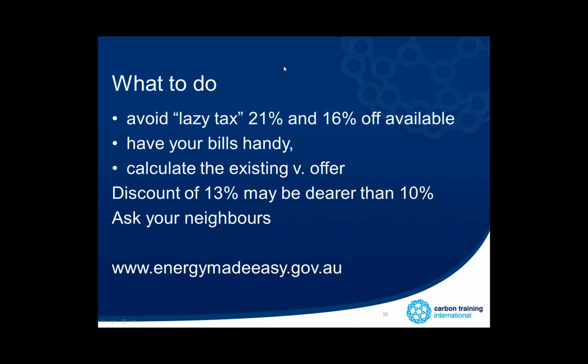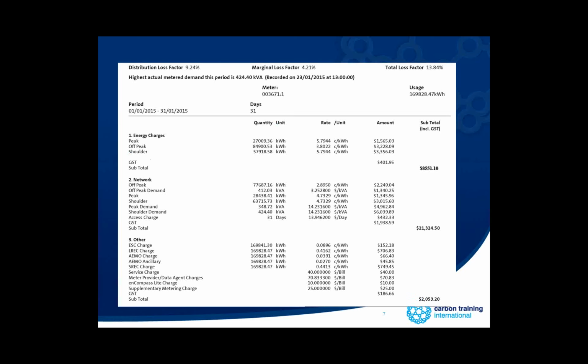Yeah, so I'll just flick back to that relevant slide with the time of use. So the demand charge refers to this kVA, and the kVA is a different way of putting kilowatts. So if I've got a 100 kilowatt electric motor, then the kilowatt reading, if I run that for 1 hour, that 100 kilowatt motor will use 100 kilowatt hours. Now, because electric motors use magnetic fields and induction to basically cause that electromotive force, some of the energy that's supplied to that motor is lost. So what you can find is that a 100 kilowatt motor should ideally put a demand on the network of 100 kVA.